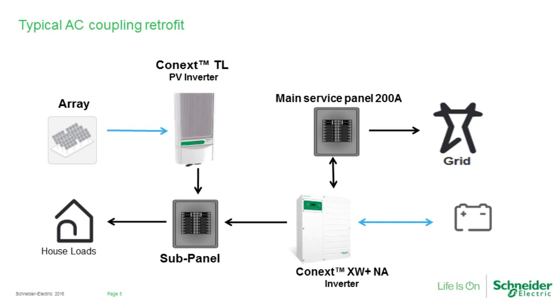Under normal circumstances, of course, a PV inverter is going to be attached to the main panel and is just simply going to push power out onto the grid. When we look at an AC coupling retrofit, we're actually putting the output of the PV inverter on the output of the Conext XW+ here in this example. And so with that sub panel, we are going to have basically two possible sources for an AC sine wave for that PV inverter to wake up. Of course, under normal circumstances, the PV inverter is just simply going to see the XW Plus as a piece of wire, because when the XW Plus is connected to the grid, it's in what we call pass-through mode. So it's just a piece of wire that's going to pass that power through on out to the grid. And what we need to have happen, though, is because the PV inverter can't create an AC sine wave, we need to have something create a sine wave during that power outage.